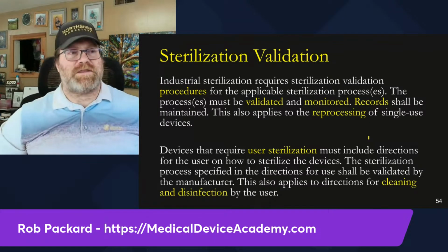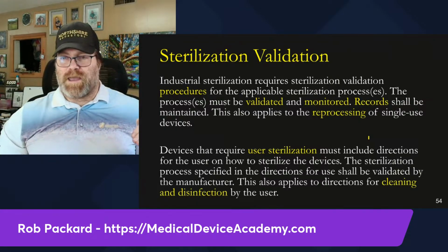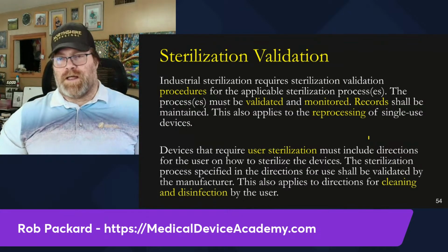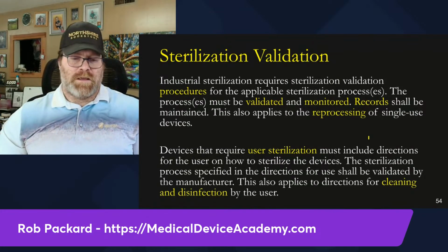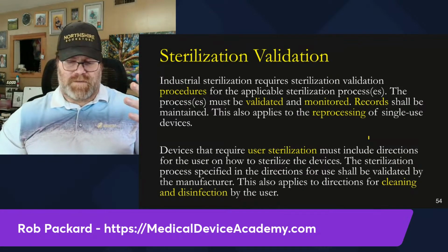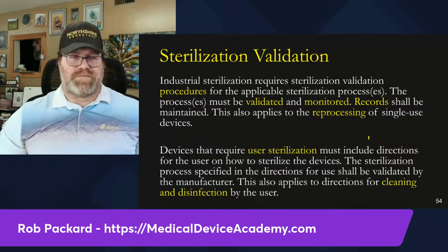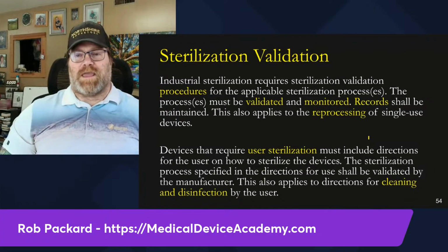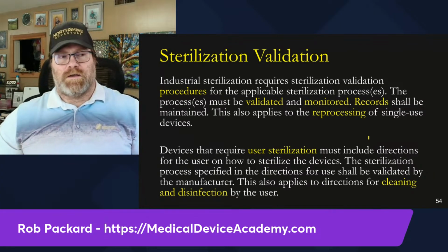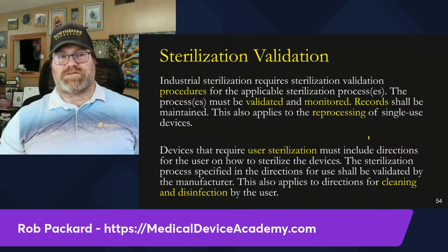For the sterilization validation, I didn't list standards here because there are tons of them. All those different category A, each one has multiple standards that apply. So if your biological indicator, your bioburden enumeration, you have EO residuals, you have overkill method 1, all these different things that you have to remember. And they send people off for training on just one mode. So just gamma, just E-beam, just EO. So depending on what method of sterilization you're going to be doing, or methods, you might have a lot of training that's required. But that's what's required for sterilization validation.